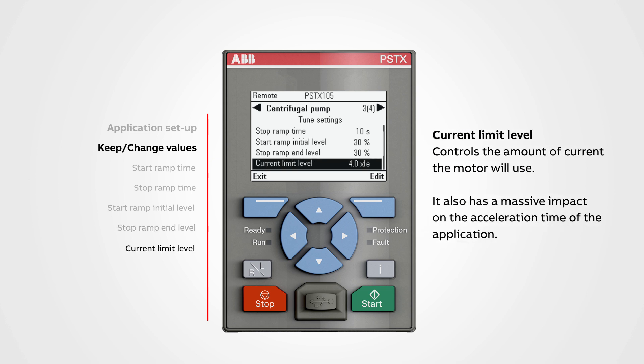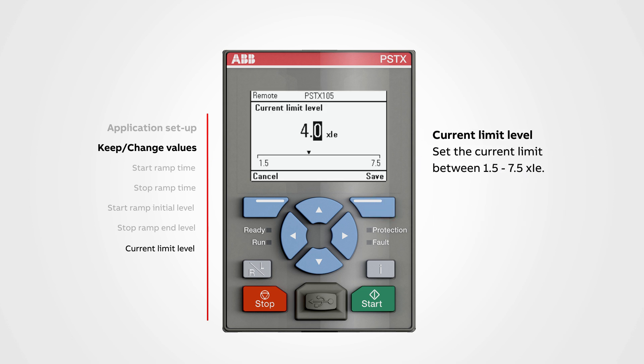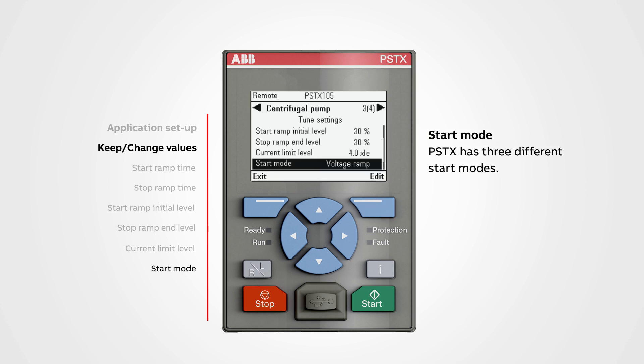Current limit level controls the amount of current the motor will use. It also has a massive impact on the acceleration time of the application. A low value will create a longer starting time, and a high number will decrease the starting time. But if the current limit is set too low, the motor will not be able to reach the top of ramp and will not start or get up to full speed. To change a value, push edit. We can set the current limit between 1.5 to 7.5 times IE. Use the navigation buttons to change the value, then push save.